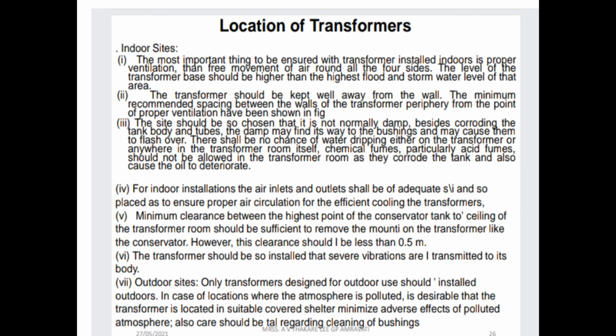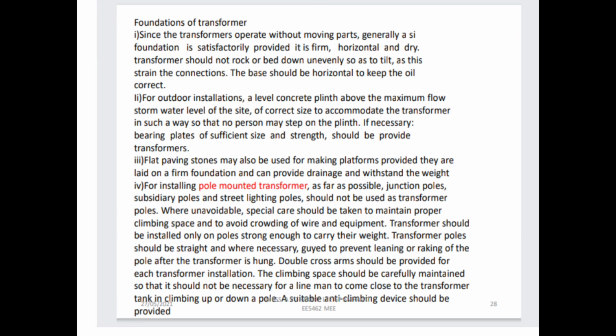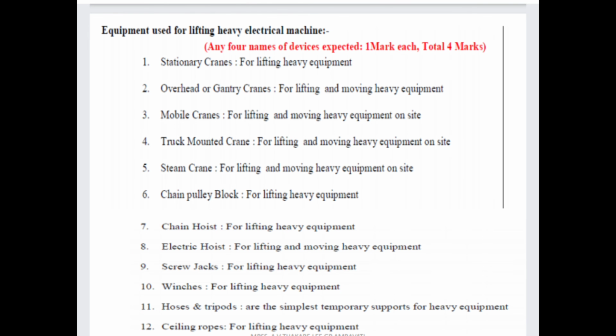Then the lining up of the belt drive. And the next point is the location of the transformer. This is an important point. So, indoor sites. The most important thing to be ensured with a transformer installed indoors is proper ventilation, then free movement of air around all four sides. The level of the transformer base should be higher than the highest flood and storm water level of that area. Next, the transformer should be kept well away from the wall. The minimum recommended spacing between the walls and the transformer periphery from the point of view of proper ventilation has been shown in the figure. So this is also the foundation of the transformer, and the equipment used for lifting heavy electrical machines.